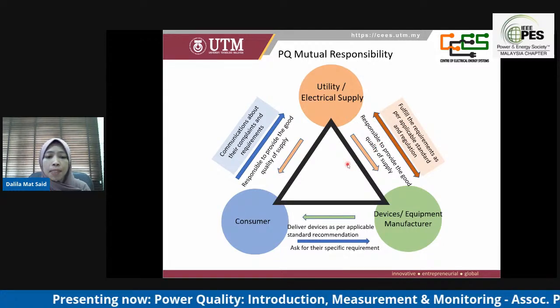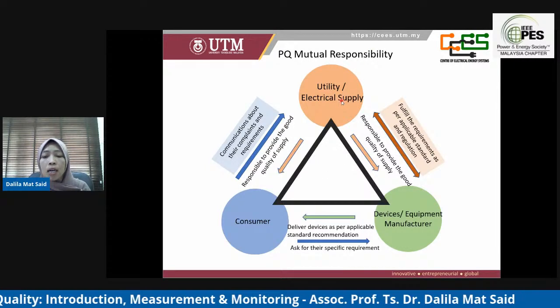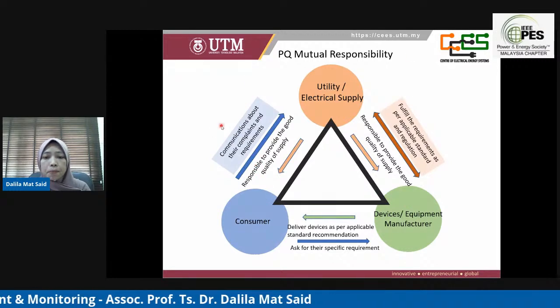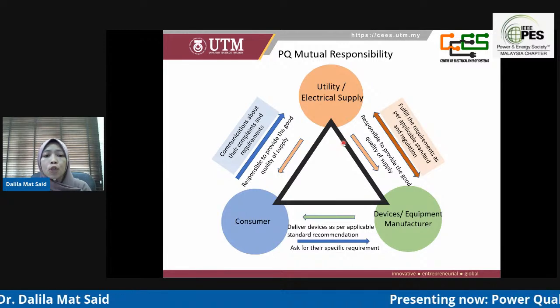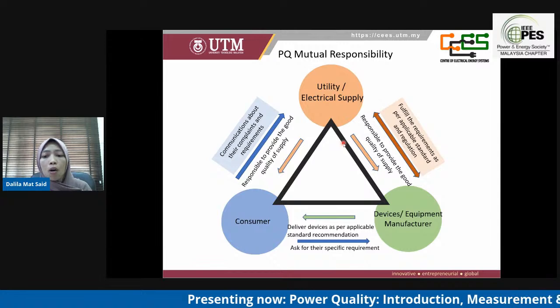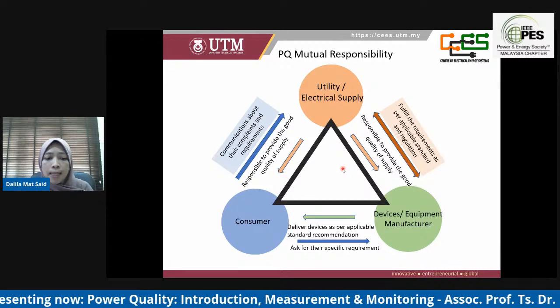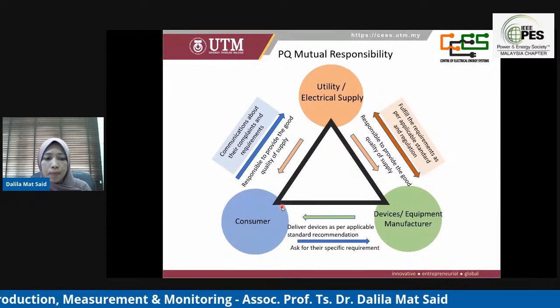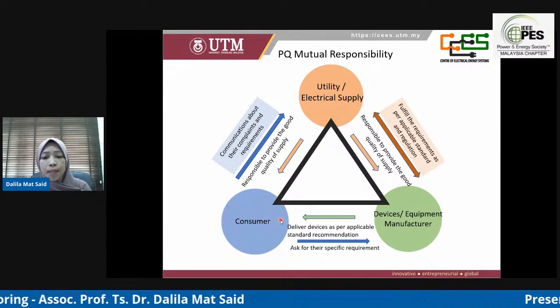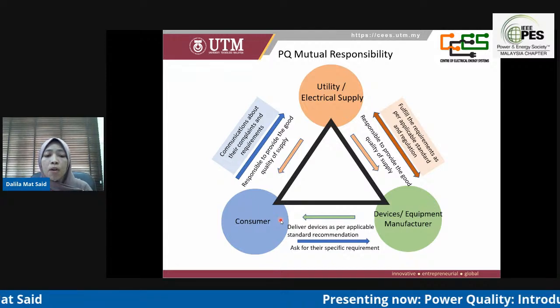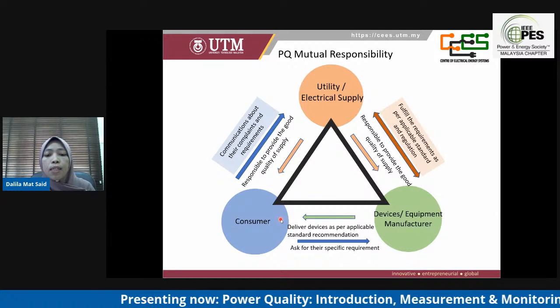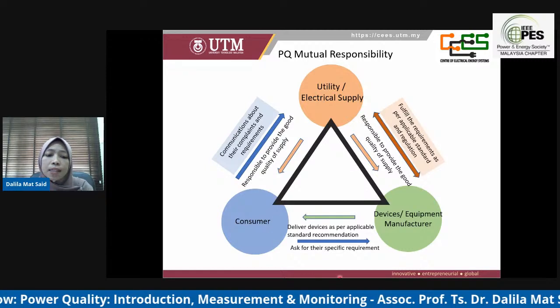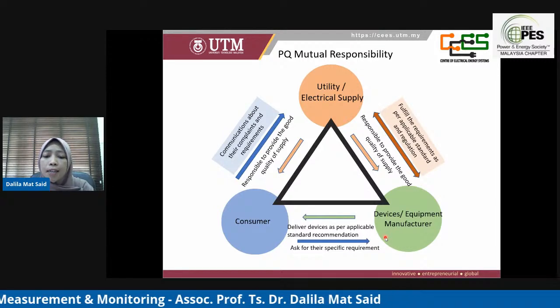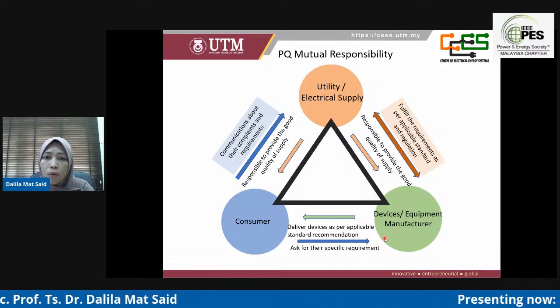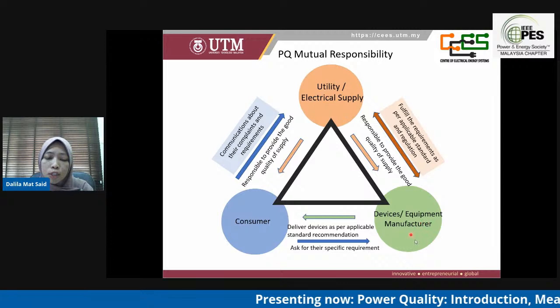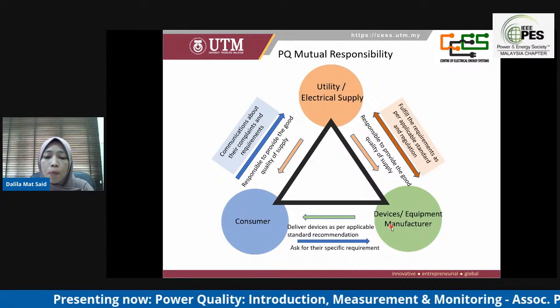This figure shows the mutual responsibility sharing on the power quality aspect among the utility, the consumer, and also the device manufacturer. From this view, the utility focuses on making sure the supply is of good quality for their customers, and on keeping electrical disturbance from affecting their equipment and their customers' equipment. As a user, they require a good quality of supply, and at the same time they need a standard to keep users from creating electrical disturbance that affects the operation of equipment owned by the utility, other end users, and themselves. Manufacturers need to produce electrical equipment that follows the standards and regulations, for example immunity levels following IEC 61000-4-11 or 4-34, SEMI F47, and ITIC, to keep their customers protected and satisfied.